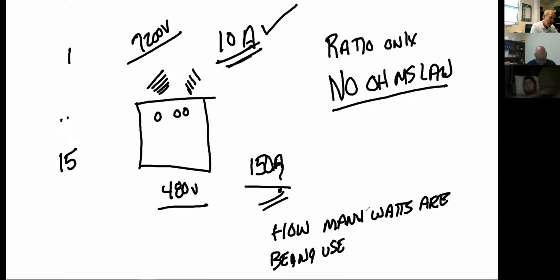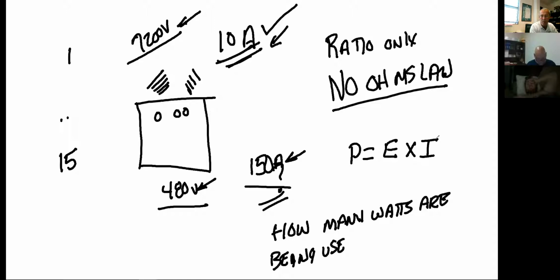What do you have supplied? I've got a voltage and an amperage, actually twice. P equals E, which is voltage, times I. What's 480 times 150? 72,000. I heard part of that. 72,000. Check this out, what's 10 times 7,200? 72,000. How about that? We could have figured it from the top number too.